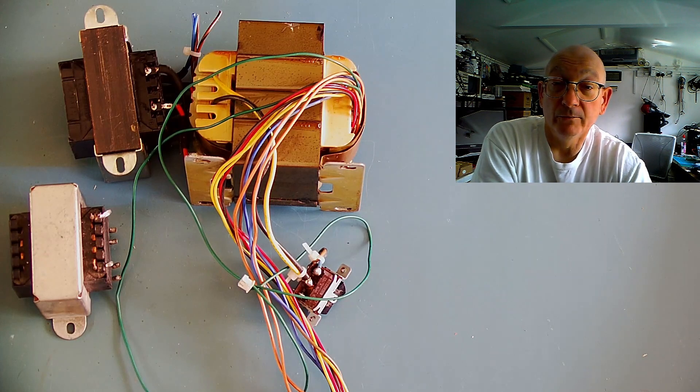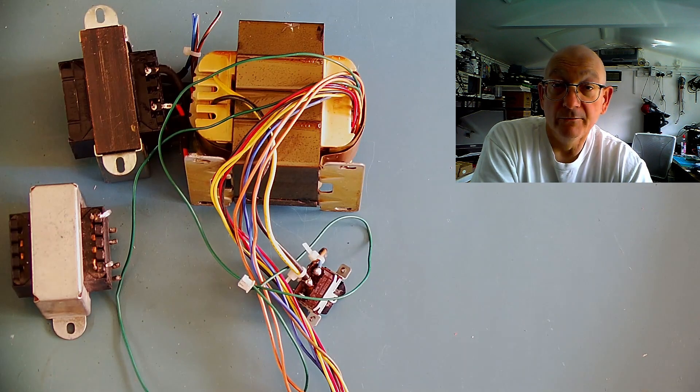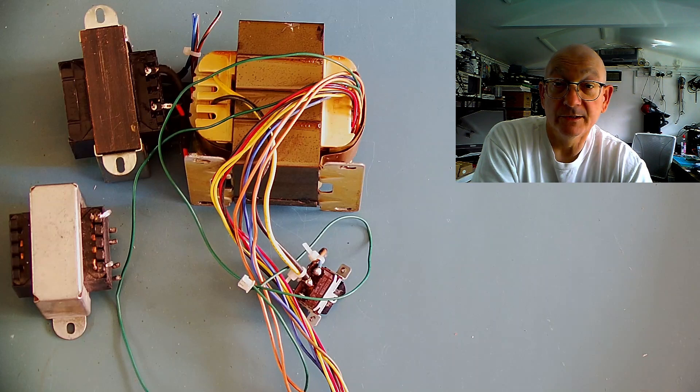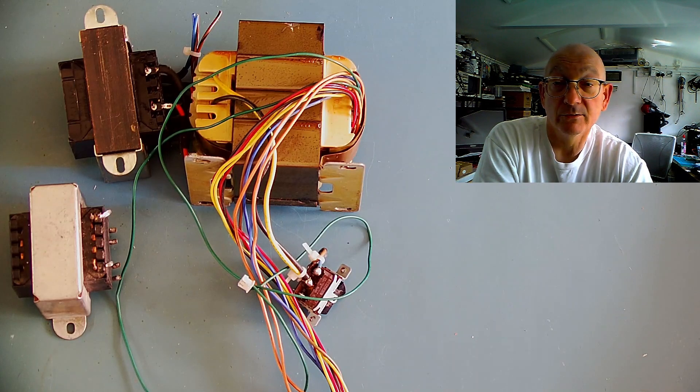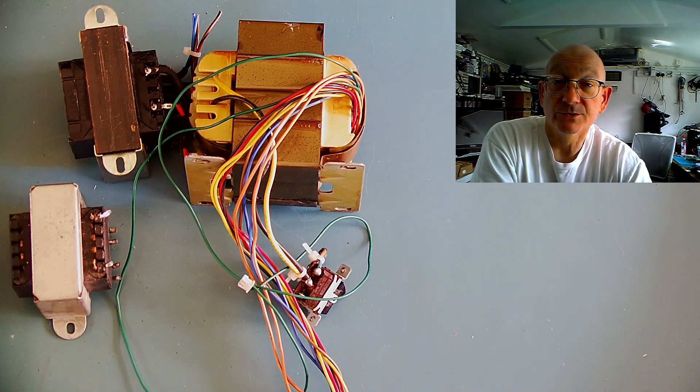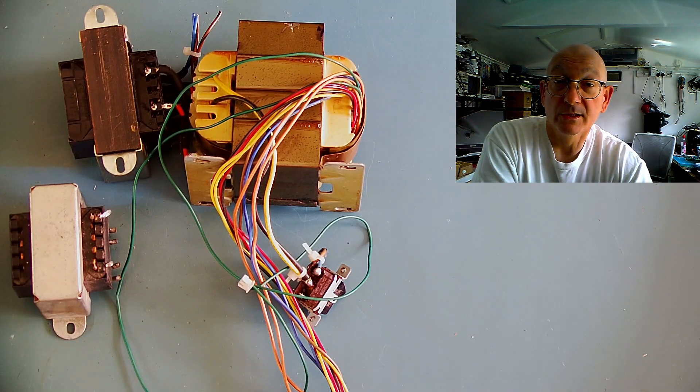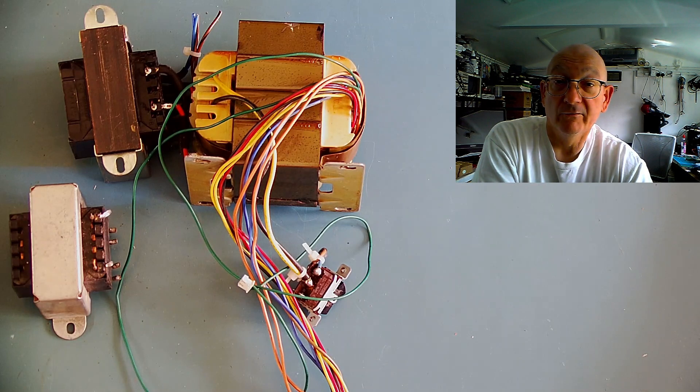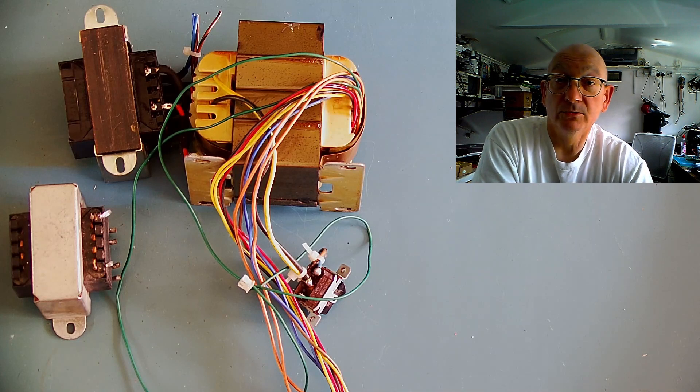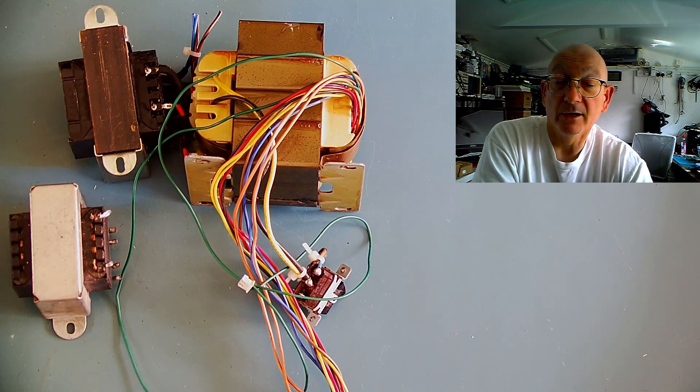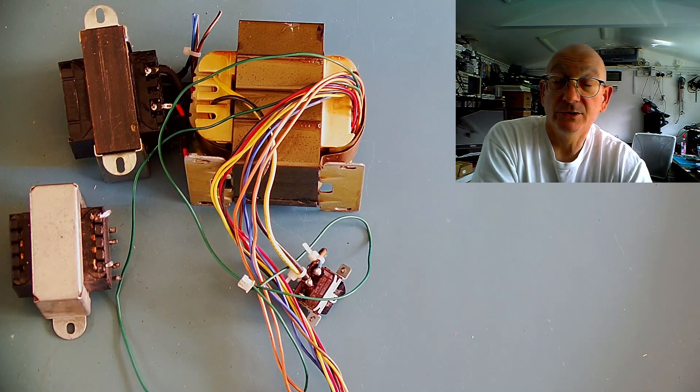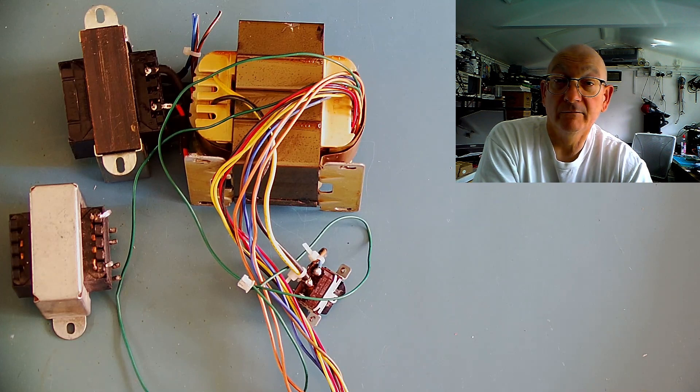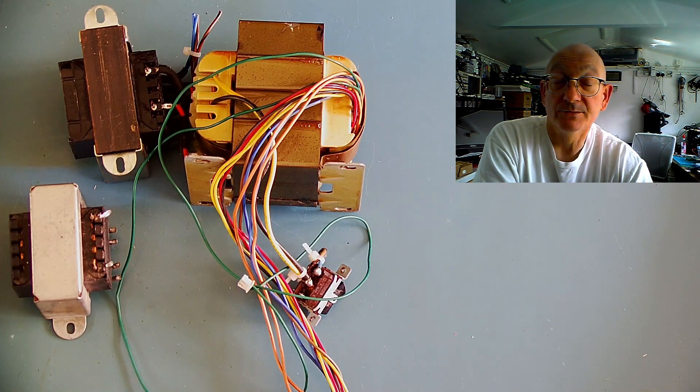The first assumption is that this is a power transformer designed to operate mainly at 50 or 60 hertz frequency. The second assumption is that most power transformers that come out of manufacturers equipment are designed to be the lowest cost possible, and therefore I am assuming that they are going to use the lower cost laminations. There are different types of laminations available and they can affect the transformer efficiency by up to 10%.